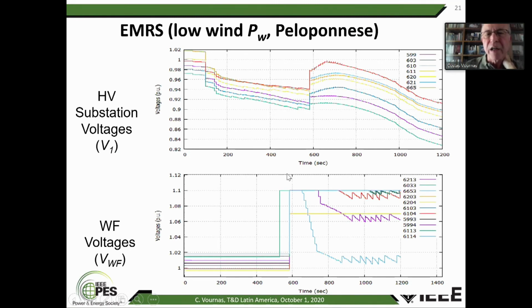As I showed before, the switch to maximum reactive support depends on their voltage. So you see one starts first, the others go here. Some stop at some intermediate point, and some reach their maximum voltage, and then they have to decrease because they came to their current limits, okay? The one that cannot reach the 1.1 is because it has reached directly the current limit.